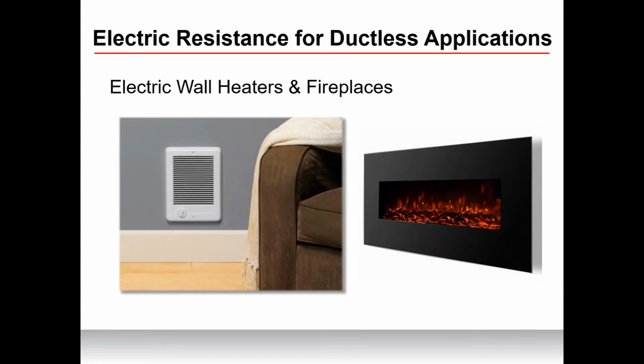Electric wall heaters and electric fireplaces are another option. We use the electric wall heaters a lot in multifamily applications. Once again, they're very simple. You can just put one in the common living area in the main living space, and it's an emergency backup if it needs to be turned on. A lot of times they're just manually operated. We use them in multifamily applications a lot for hallways or just common areas. An emergency backup source, or to keep stairwells in multifamily applications just up to temp, maybe 50 degrees, just above freezing since no one's living in that space.